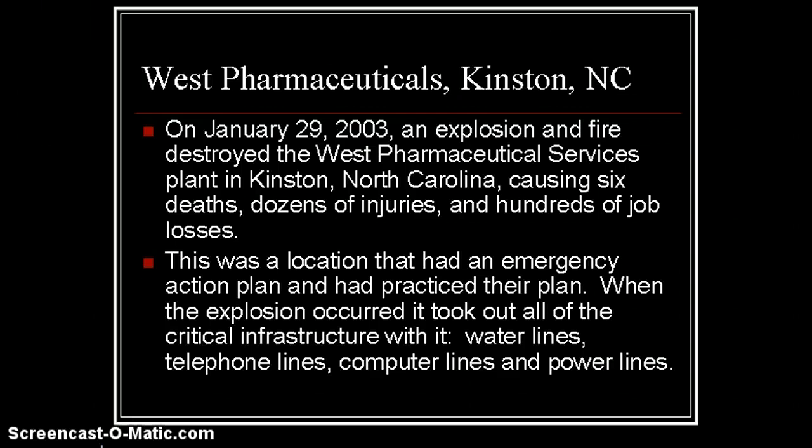But the big thing that this one brings to the table as far as a case study is that what do you do when you've done everything right and it all blows up? For this particular incident, their water lines were busted. They got blown up. So they had no water coming to the plant for fire suppression. The telephone lines were taken down. The computer lines were taken down. Power lines were taken down. So they had to resort to other things.